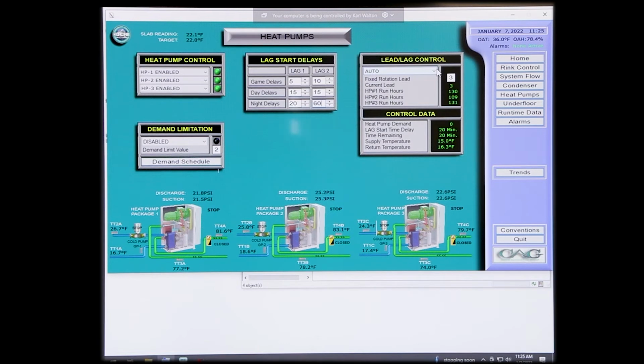Lead lag control. Right now I'm currently in auto mode, which means it'll flip from base. Current lead right now is compressor 3, so it's going to start compressor 3, then compressor 1, then 2. The next temperature cycle, it'll start compressor 1, then 2, then 3, as needed, based on demand. It'll tell you here, you've got run hours. You've also got your hour meters down on the package. You've got heat pump demand here, based on how far off set point we are. That's where you'll see a demand here.